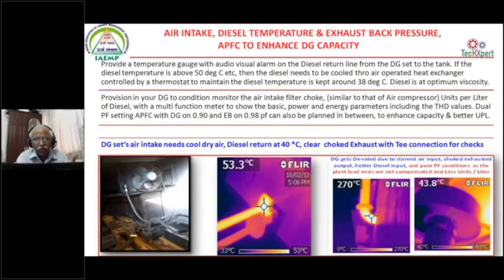This will give diesel savings of almost 4 to 5%. We have seen the savings. We have seen this in TVS Group, and we have suggested it to many others, and they have implemented it and they have seen the savings. The return diesel temperature should be maintained at 40 degrees instead of 55 or 60 degrees.